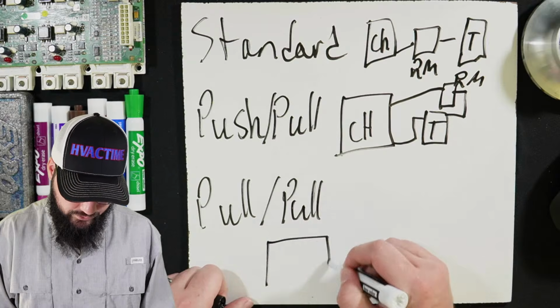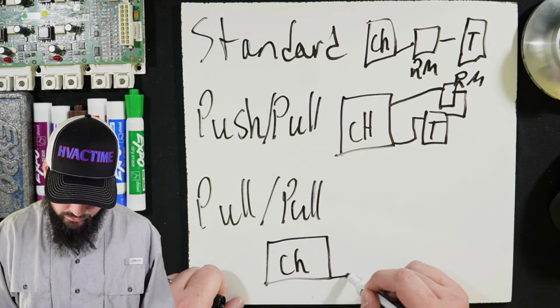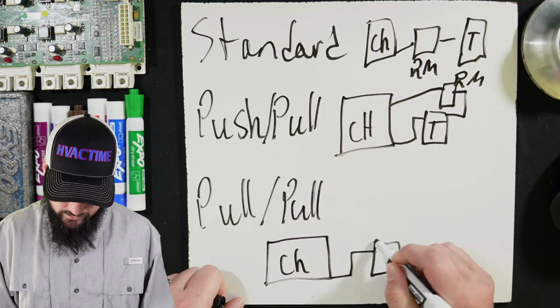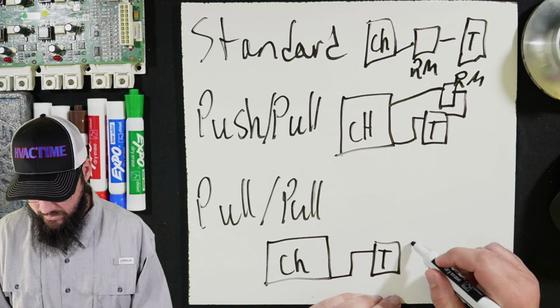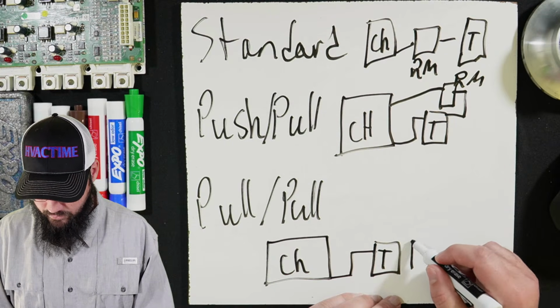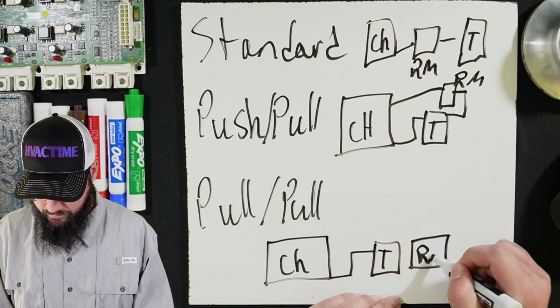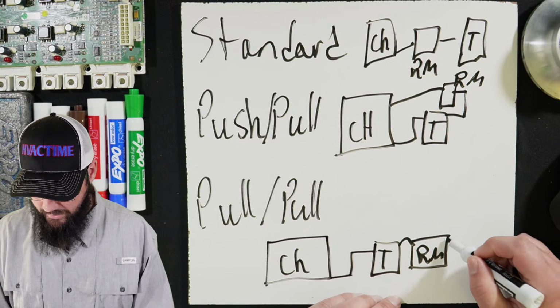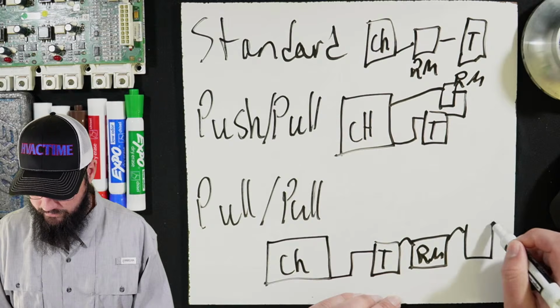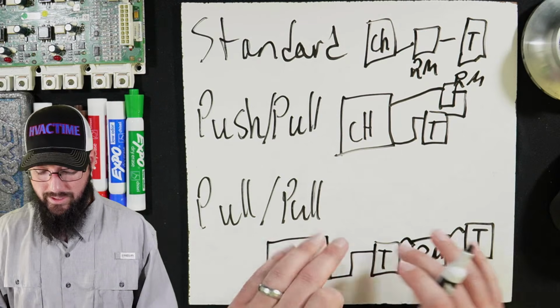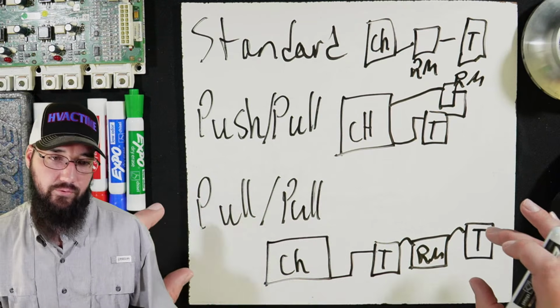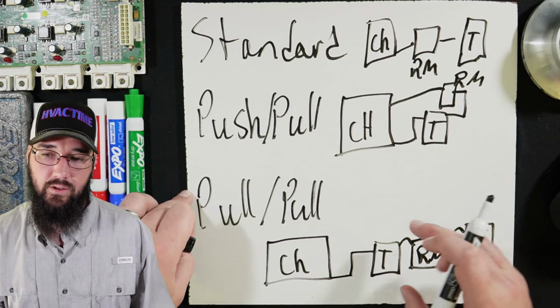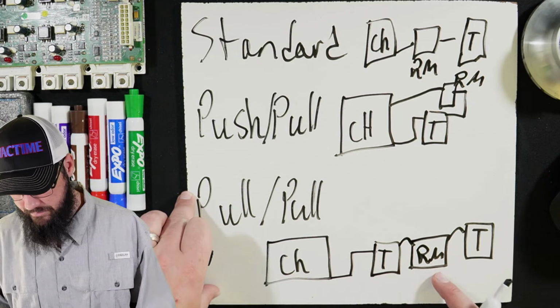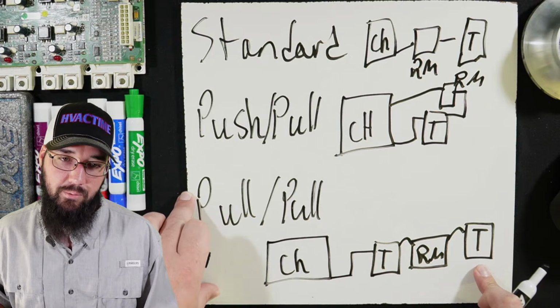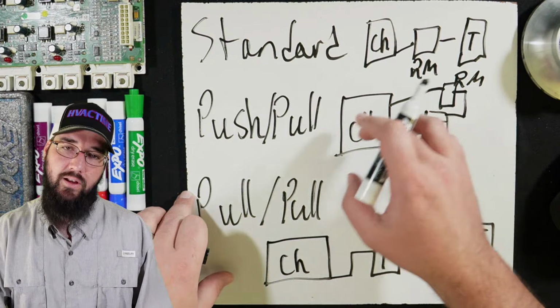So we're still going to have our chiller. We're still going to pull liquid out the bottom of the chiller into a liquid capture tank. But then we're going to go out of the vapor port into our recovery machine, and then out of the recovery machine into a vapor capture tank. And that's the whole chain of the pull process. So we go from chiller to liquid capture, recovery machine, then to vapor capture. And instead, it's just not cycling through.